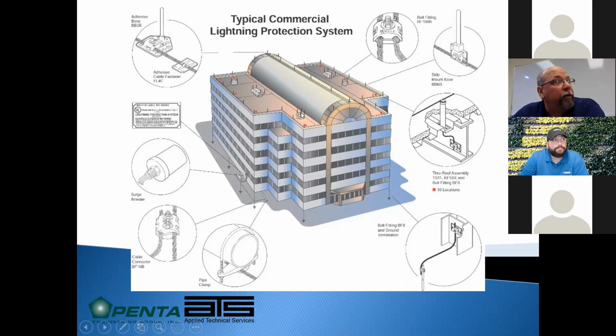And depending on how tall and the geometry of several things we'll get into in a little bit, we have air terminals on mechanical equipment on the roof, and everything's interconnected with two paths to ground to the perimeter loop. And the air terminals are within 2 feet of the perimeter edges of the building. And then at least once for every 100 linear feet of building perimeter, there'll be a down conductor, which is a cable that takes this energy all the way to the ground, where it's interconnected with ground rods.